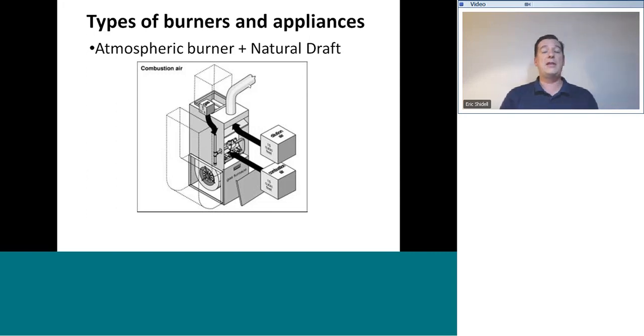Dilution air is added to those flue products to essentially lower the dew point, meaning condensation is going to be less likely to occur. Natural draft appliances need this dilution air coming in, otherwise it would always be raining in the flue.